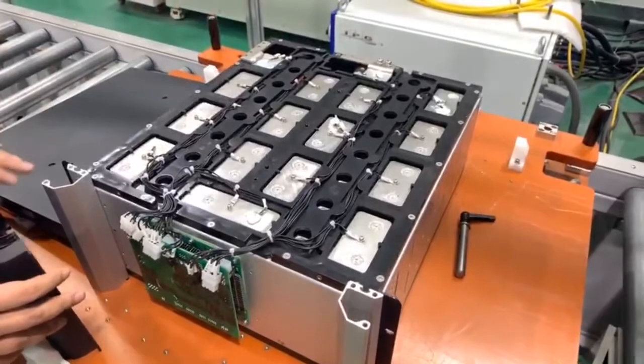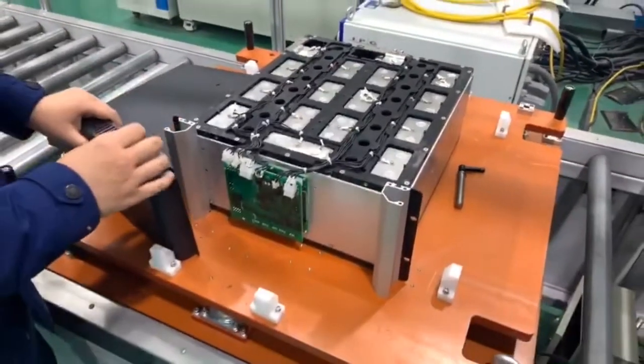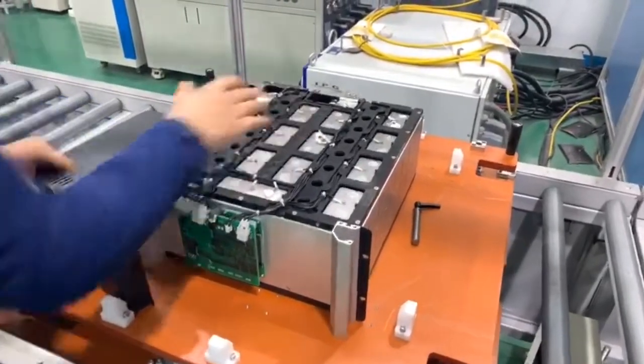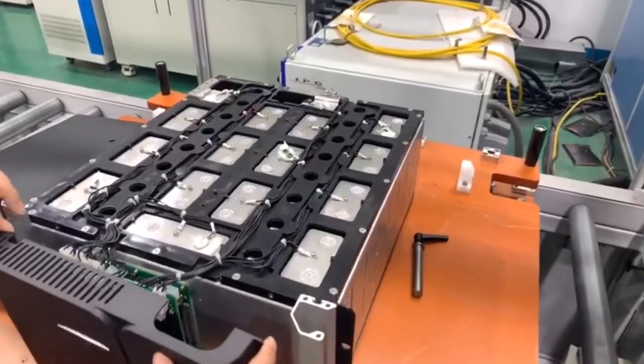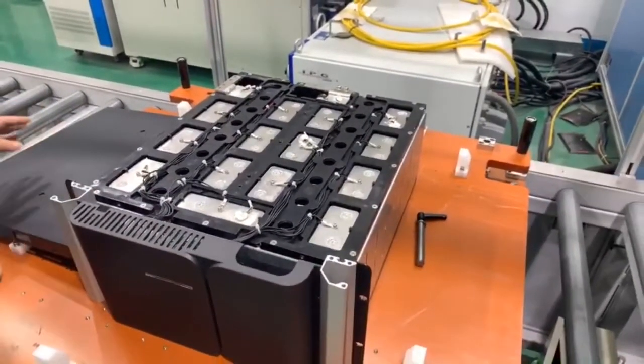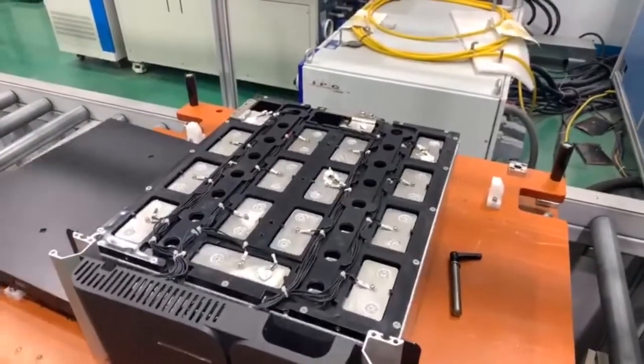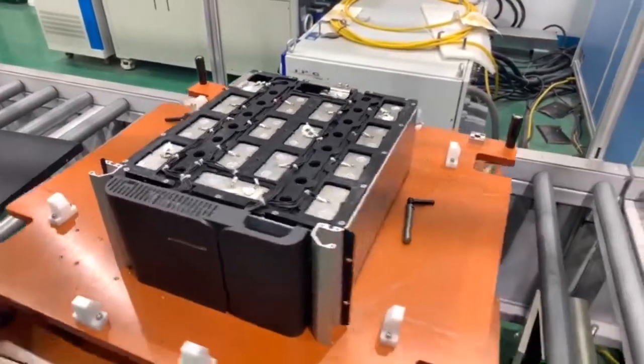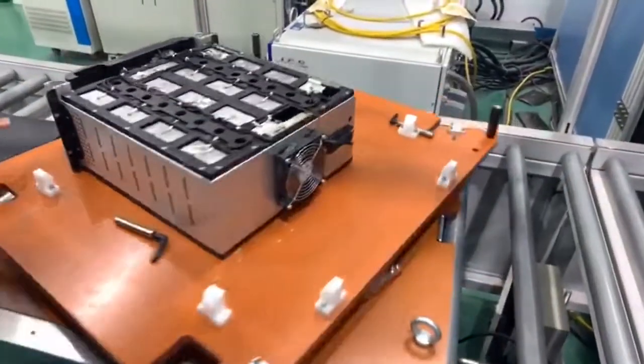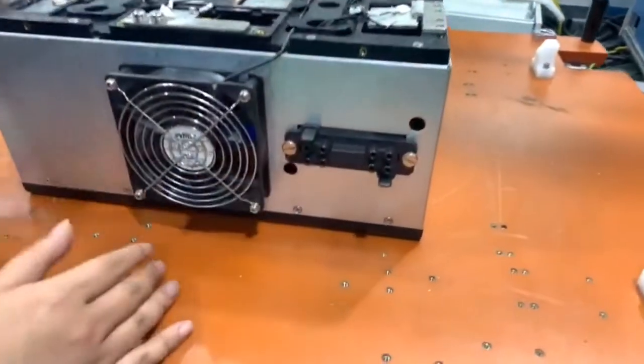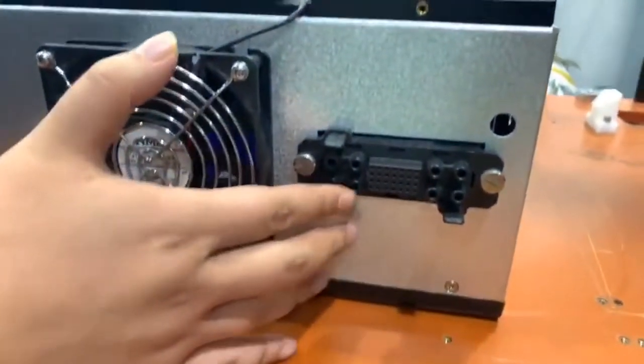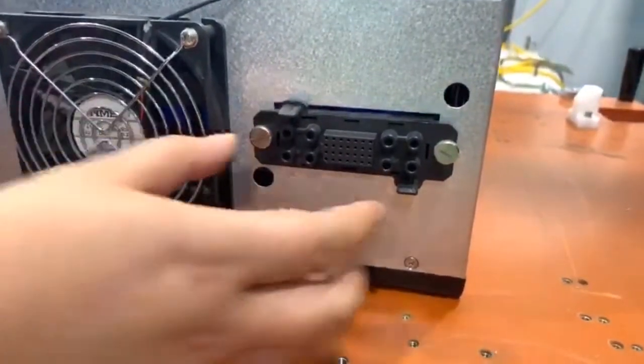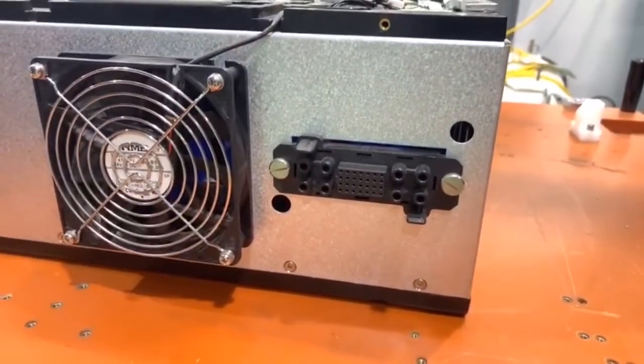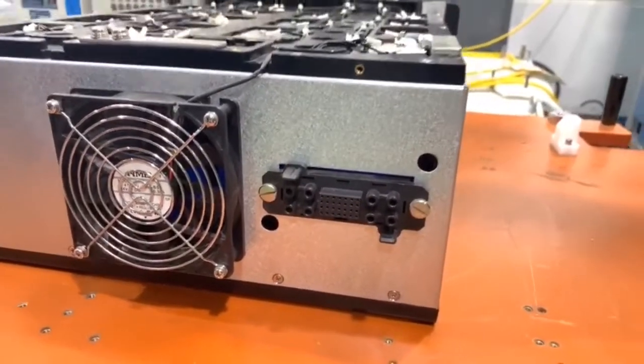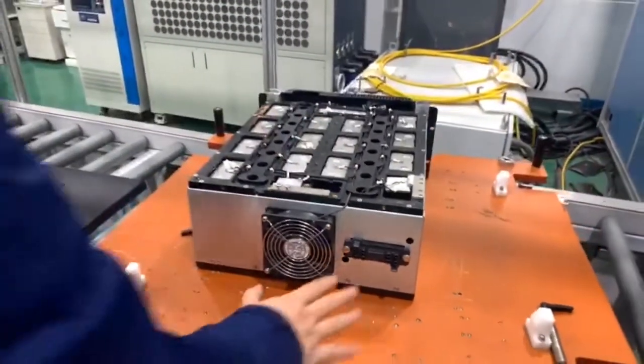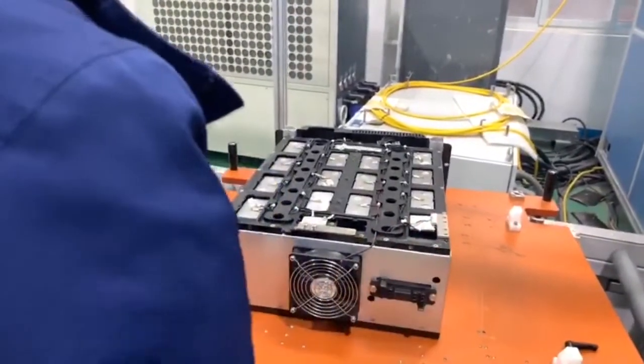In our battery module, we can have 3 up to 8 temperature sampling points to ensure the battery system prevents overheating or overcooling. There's also a special design on the backside - this is the battery module connector, called the JMD connector. The power cable and communication cable all connect here, and we can use the JMD connector to connect to the battery cabinet very easily, like a hot plug. Wrong connection will never happen with this connector.